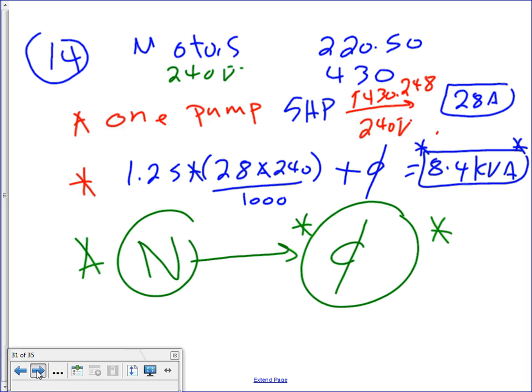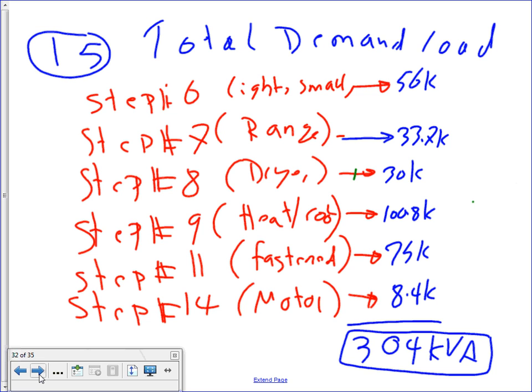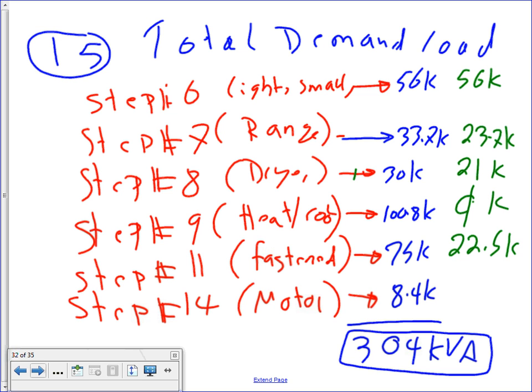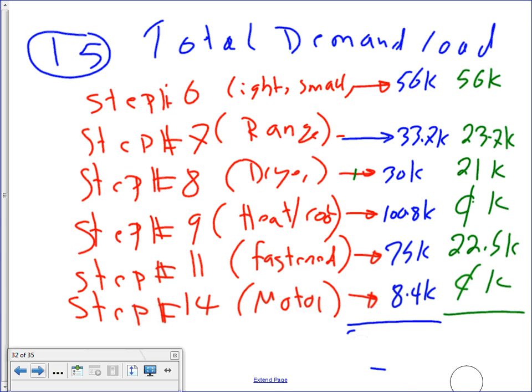The last thing, ladies and gentlemen, is going and adding them. Now we're going to go add them. Right here, I'm going to put them right next to each other. I have 56K. This is 23.7K. For this load, 21K for the dryer. For this load, it's 0 fluffy K. For fasten in place, it's 22.5K. For the motors, it's 0K. And we're going to add them up. Let me move them just slightly so I can put this one. 304 kVA. That was the size for the phases.